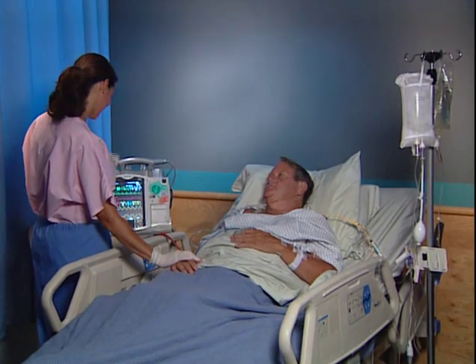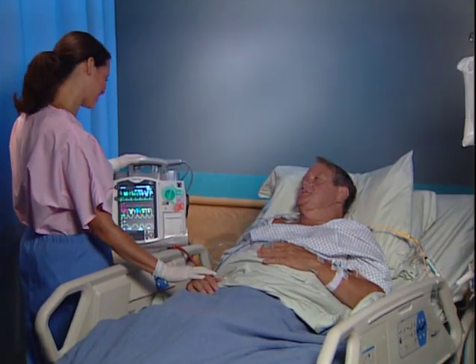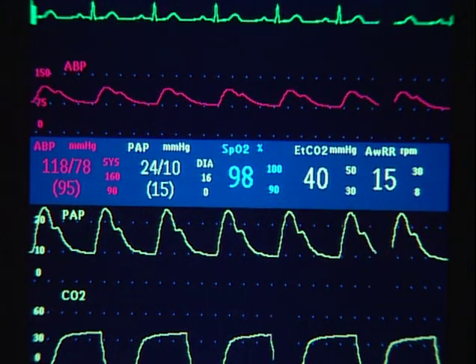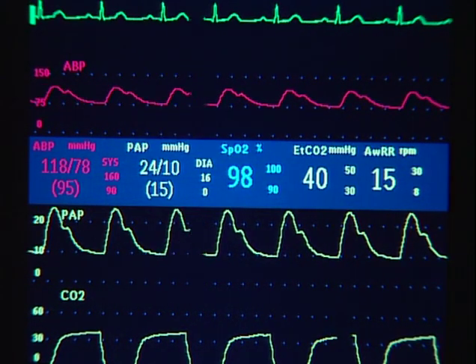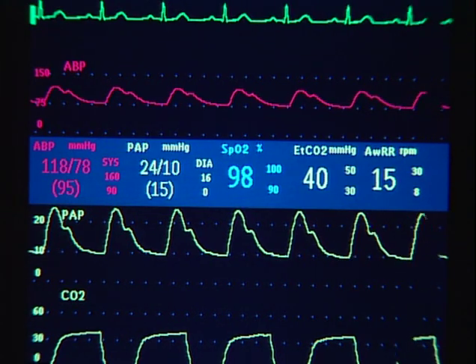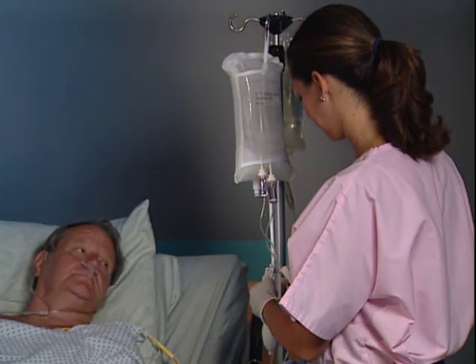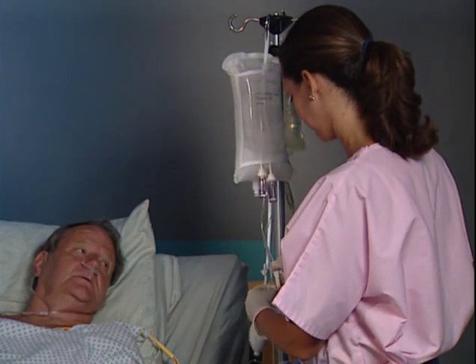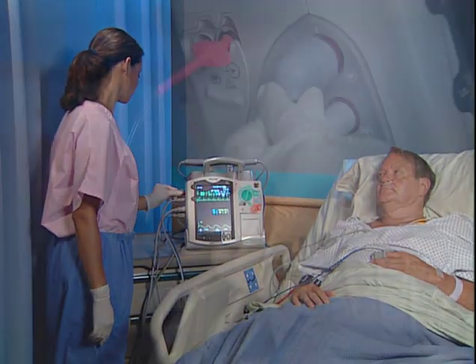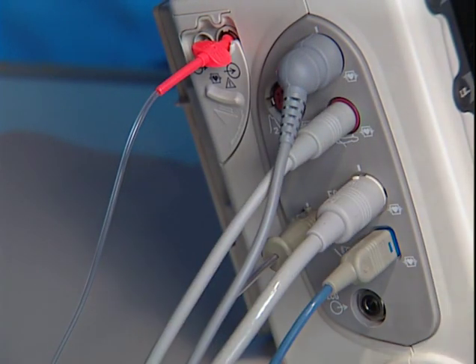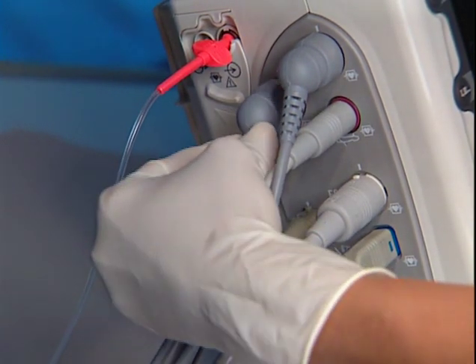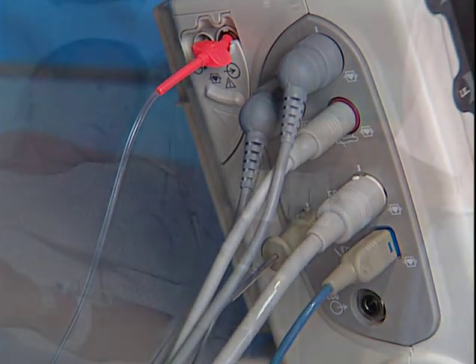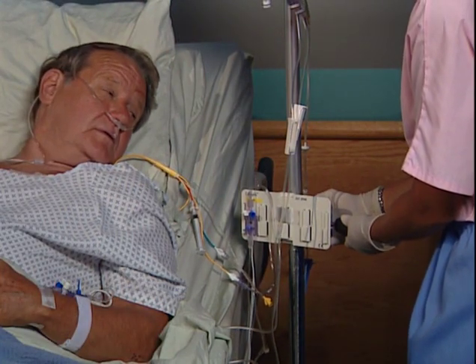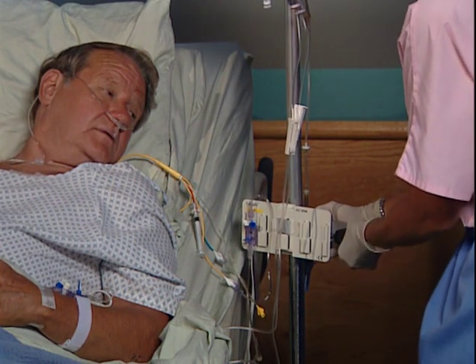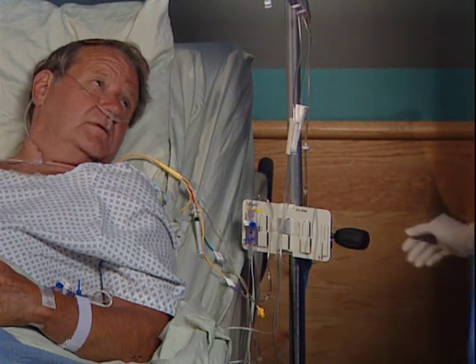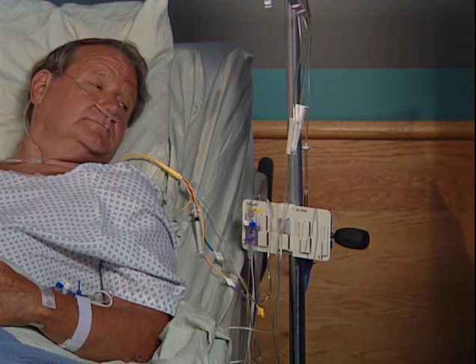The MRx offers optional invasive pressure monitoring capability with 2 channels of real-time continuous pressure measurements and waveforms in monitor, manual defib, and pacer modes. To begin, prepare a pressure line according to your hospital's standard procedure. Connect the pressure cable to the Heartstart MRx. Make sure that the transducer is level with the patient's heart, approximately at the level of the mid-axillary line. If measuring intracranial pressure, follow your hospital's protocol.